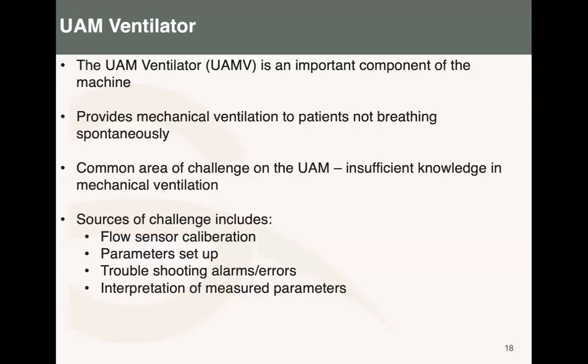The machine also comes with a ventilator, which is important, since sometimes we have long cases that last 3-4 hours where you cannot hand-bag, so you have to use the machine. My experience is using the vent, because with the vent you know exactly how much volume you're providing to the patient. So I always prefer to use the vent, especially when giving TIVA. The machine comes with the vent so you can give your anesthesia comfortably.